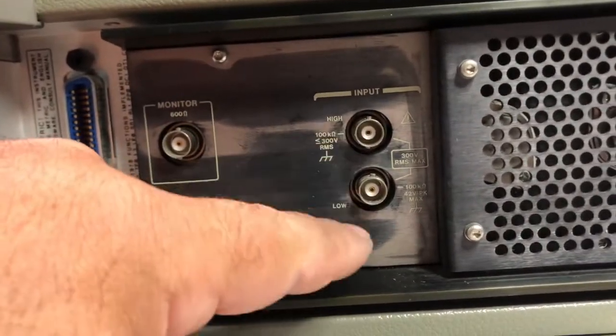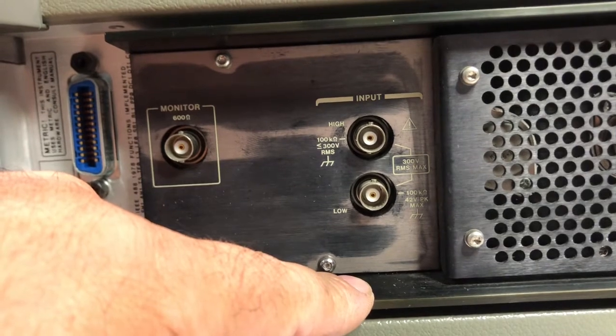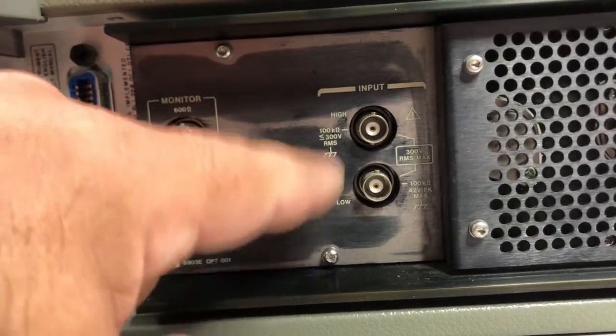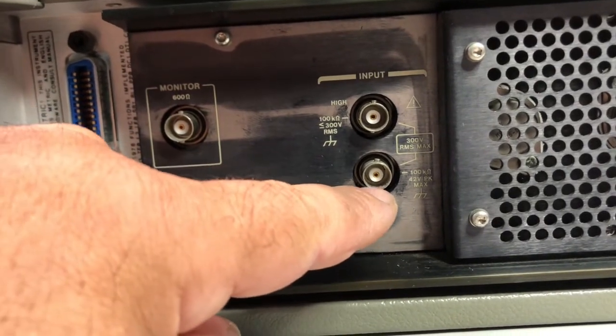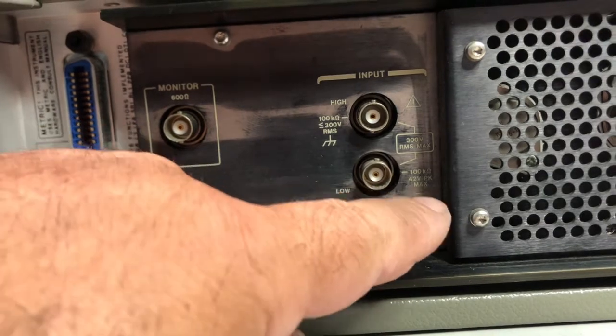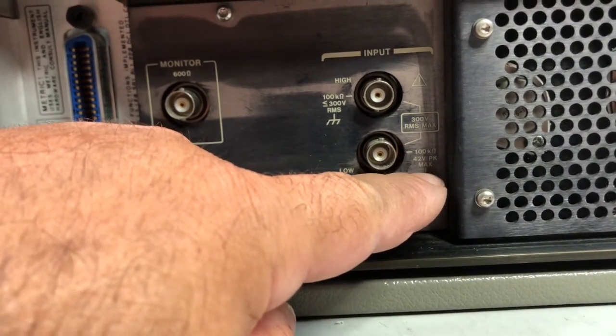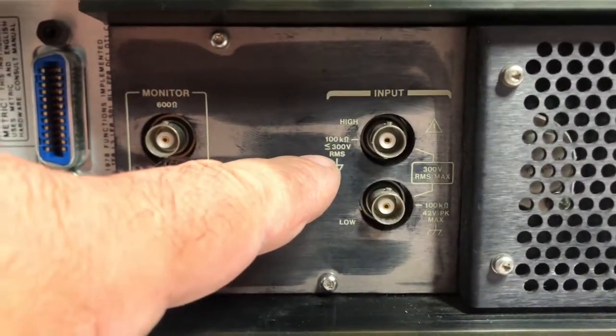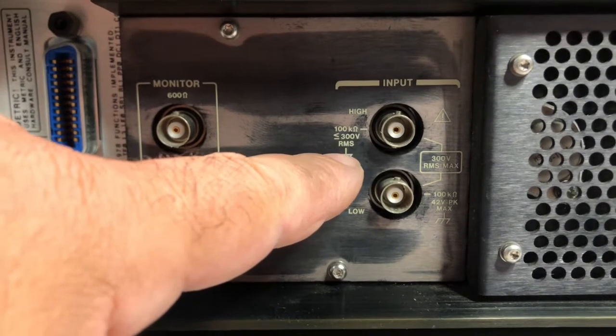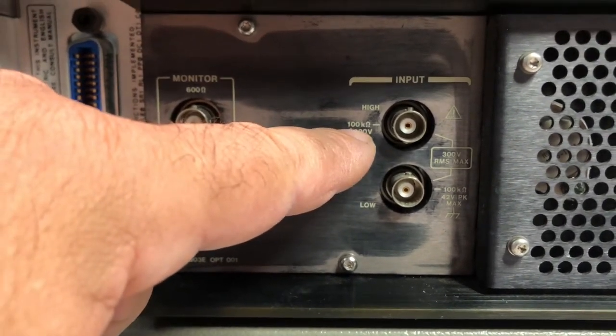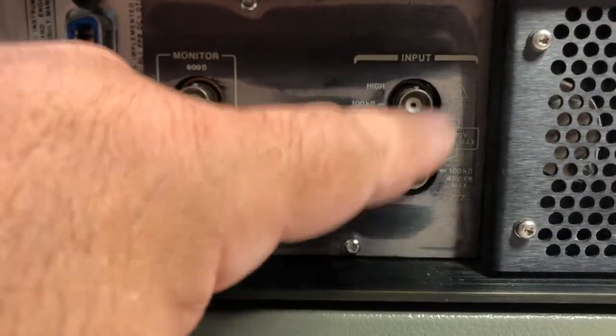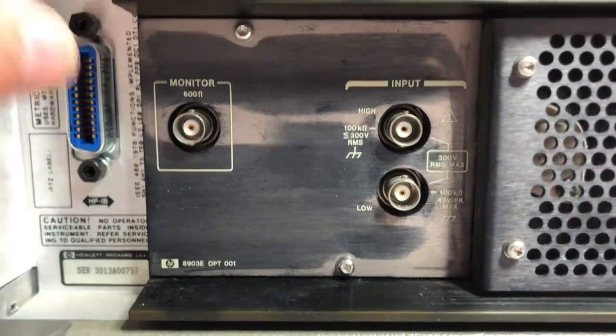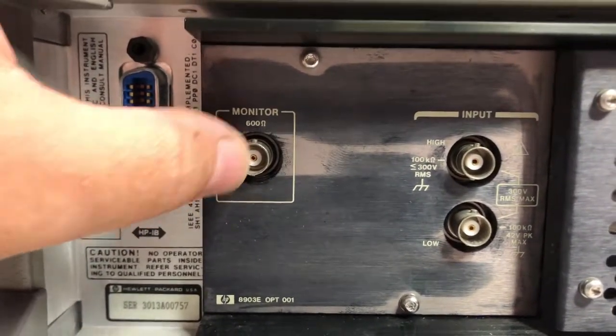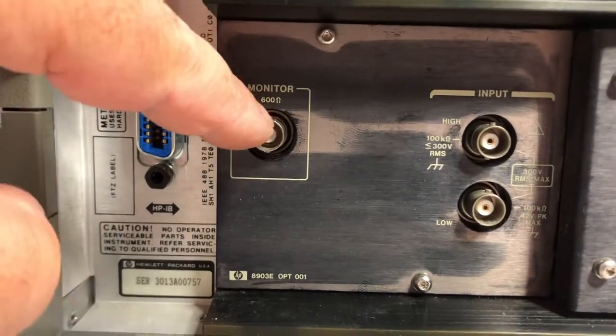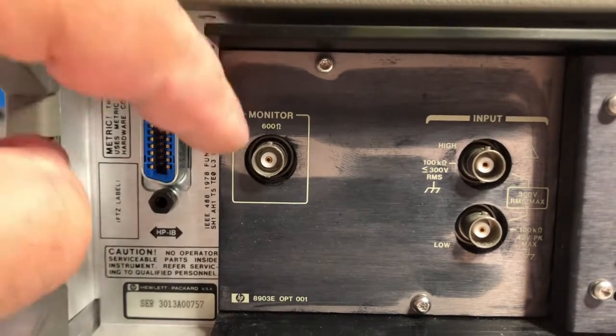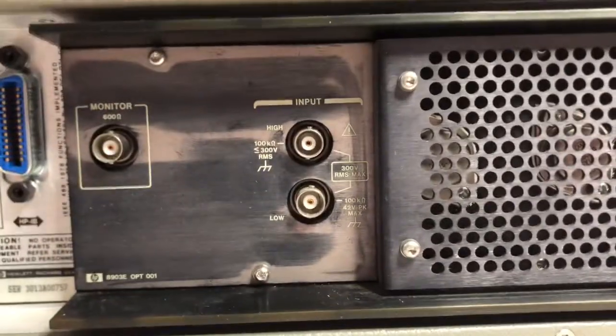we have two different inputs here that are labeled low and high, so I don't know if it's related to volts. Yeah, this is 42 volts peak maximum, and this is up to 300 volt RMS, 100 kilo ohm. Both inputs have 100 kilo ohm impedance, I believe. And this is the 600 ohm monitor output, so we can plug to an amplifier and a speaker and hear the actual signals that are fed in the instrument.